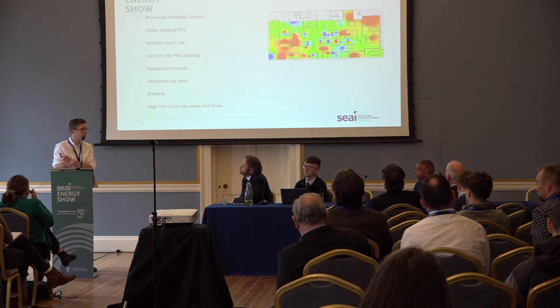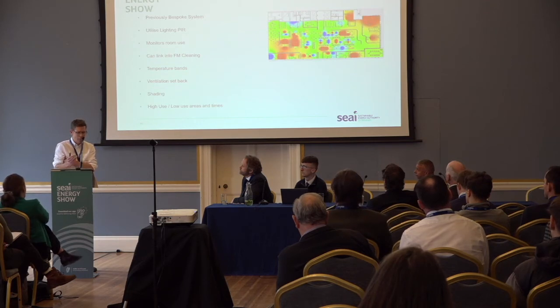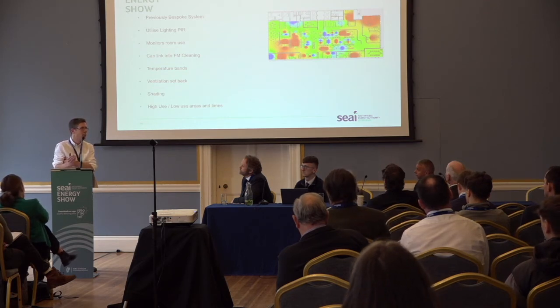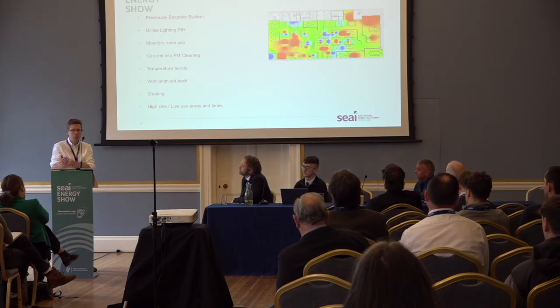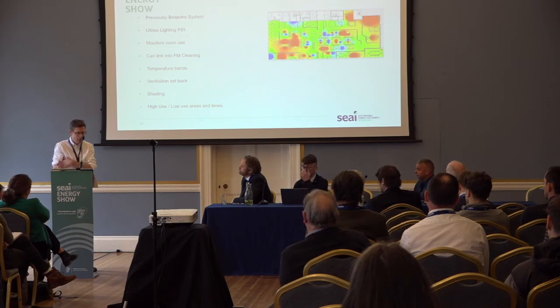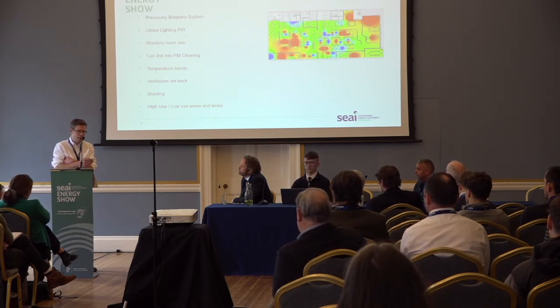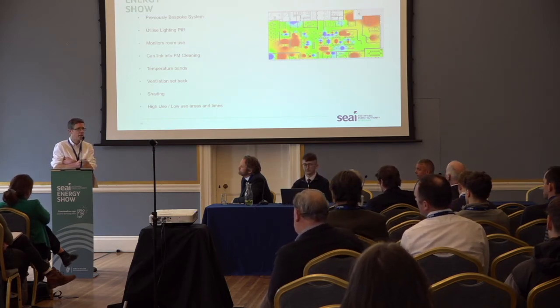So we can use DALI lighting systems to get some information back - was the room booked, and is it actually used? If the room is unoccupied, we can set back the temperature in that room, and pre-purge rooms for some of the larger meeting rooms and spaces before people come in, so they're ready for occupation. We can also see if general areas of the office are actually used.